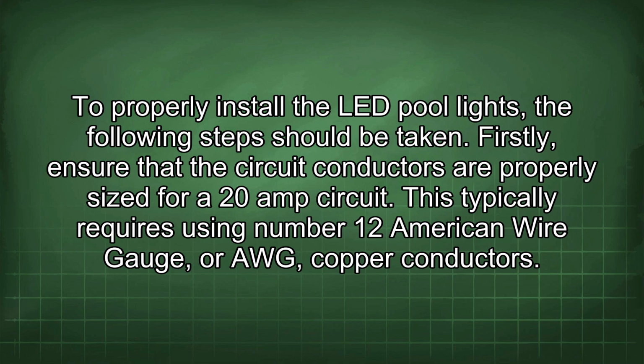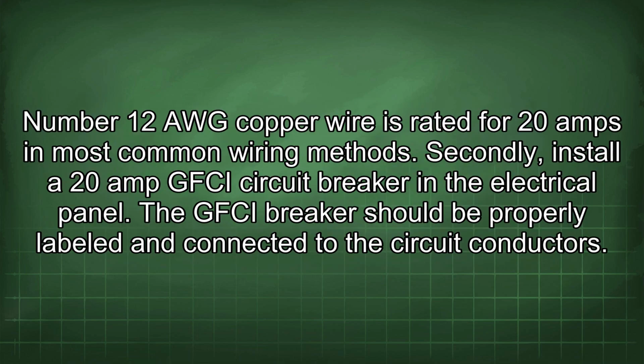Firstly, ensure that the circuit conductors are properly sized for a 20 amp circuit. This typically requires using number 12 American Wire Gauge, or AWG, copper conductors. Number 12 AWG copper wire is rated for 20 amps in most common wiring methods. Secondly, install a 20 amp GFCI circuit breaker in the electrical panel. The GFCI breaker should be properly labeled and connected to the circuit conductors.